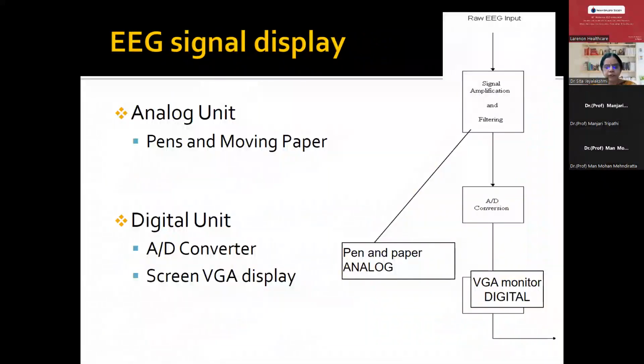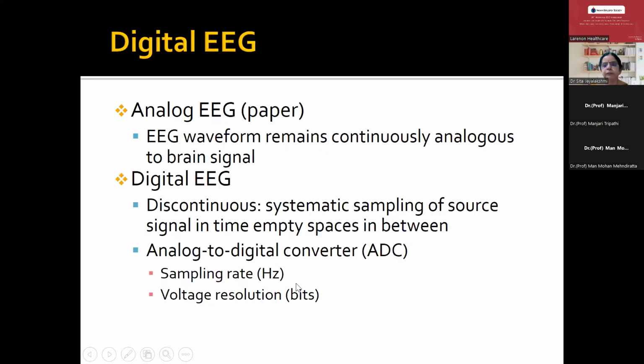So this is how it occurs. So once we know that the amplifier has a high frequency filter, a low frequency filter, as well as the notch filter, now we understood how we place the electrodes on the surface and how they come onto the junction box and then to the amplifier. And after that, how is it displayed onto the surface of the monitor? Normally, in the analog unit, it was always a pen and paper, but nowadays we do not have it. So coming to the digital unit, how does the recording come nicely as the alpha, beta, delta waves? The digital unit has something called the A to D converter. And in addition, there is a VGA display.